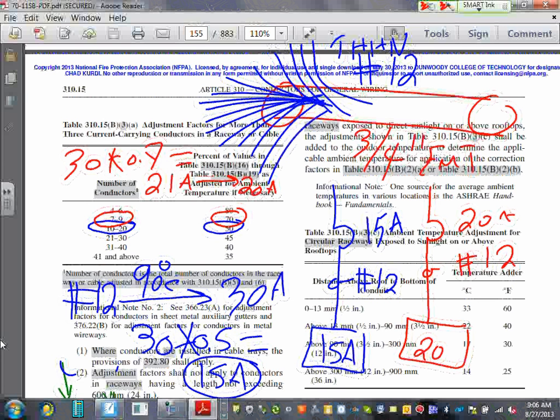Can I use 21 out of that conductor even if I want to? No. Why? This conductor is limited to 20 under normal operating condition. Do you see why a lot of engineering specs will say no more than 9 conductors in a conduit, especially for branch circuits? This is derating based on bundling. They call it bundling, grouping the branch circuits together. Derating based on bundling, grouping the branch circuits together.